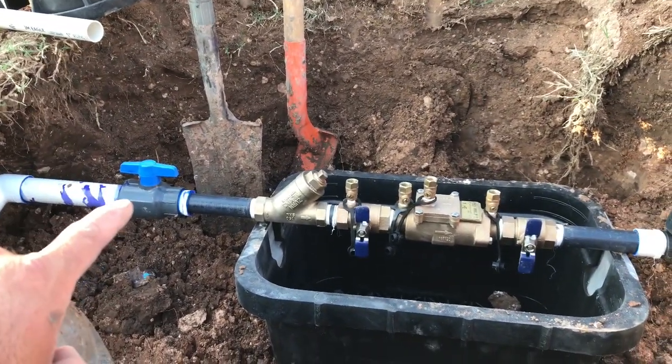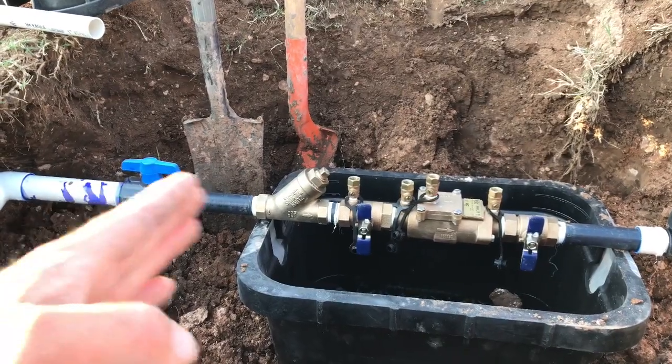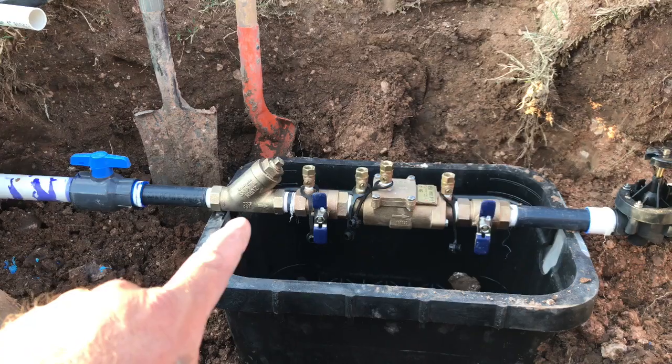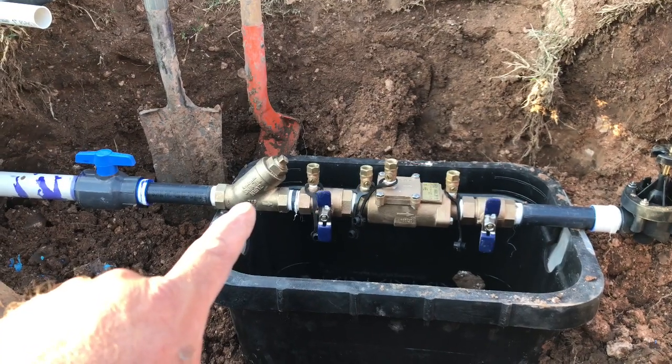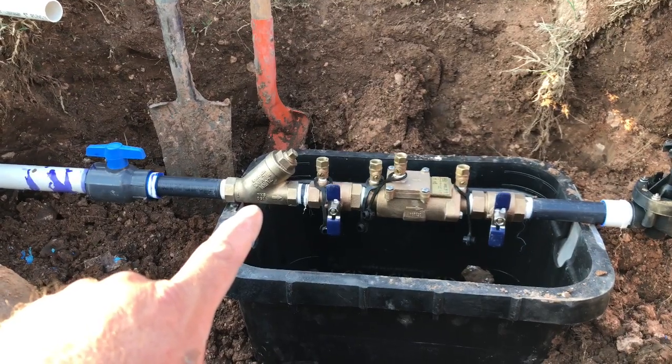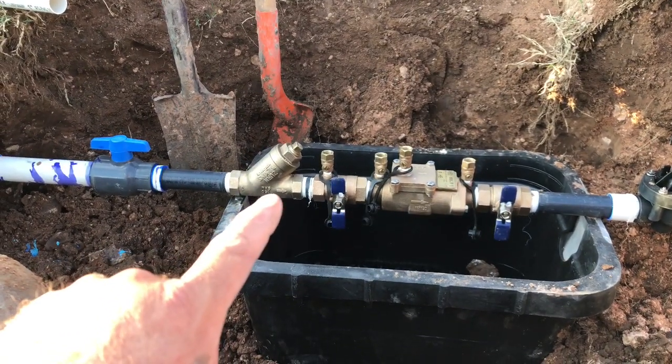As you can see here, we've got our shutoff valve — the isolation valve that goes before the double check. I've also got our Y-strainer here. I like to use the brass Y-strainers because they're actually rated to be under pressure. Those cheap plastic ones you use for drip fittings are not good to use in this application.